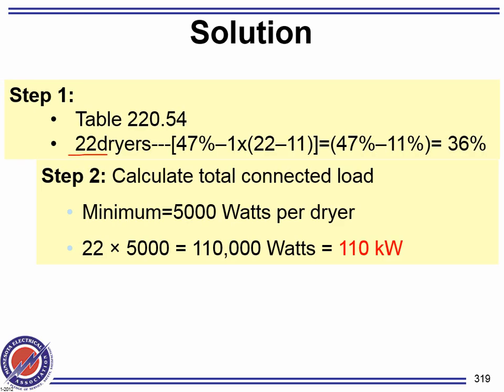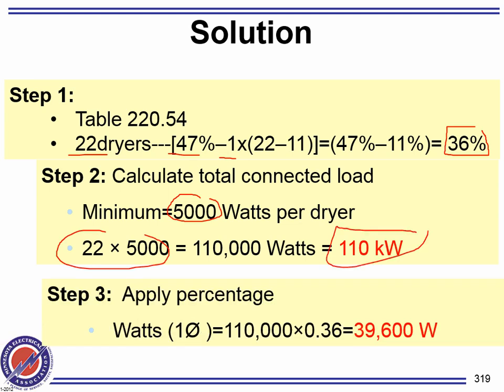For 22 dryers, gentlemen, 47 minus 1 times 22 minus 11. That formula that we just looked at? That'll give me 36. Everybody understand how we did this fuzzy math? One percentage for every dryer exceeding 11. So 22 minus 11 times 1 gets you 11. 47 minus 11 gives you 36. You have to use the 5,000. So 22 times 5,000 gives you this amount. Now you cut it by this value, and that's what you get. Can you imagine the difference between sizing?